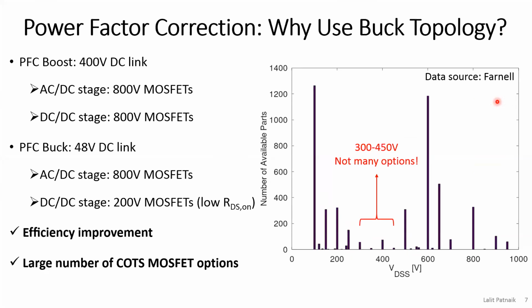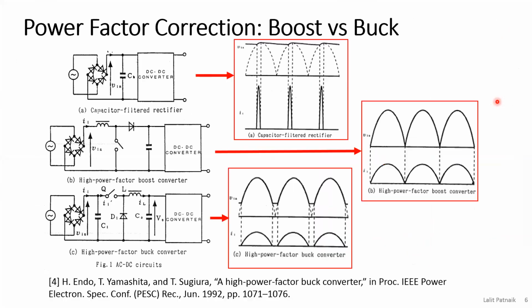The blanking period in grid current will be a function of output voltage -- if output voltage increases, the blanking period will also increase, and therefore current quality drops. That is correct. Do you have any comment on the extent to which the current quality will be acceptable? In fact, the choice of the DC link voltage is decided by this factor as well.